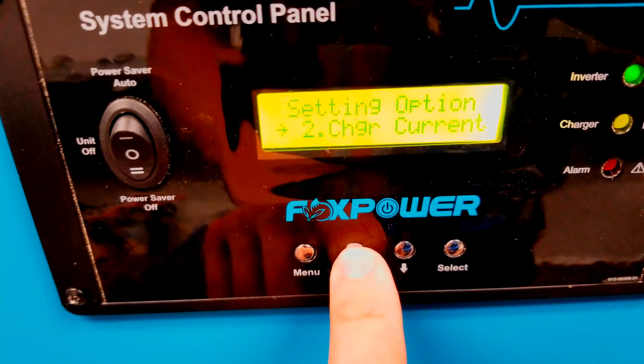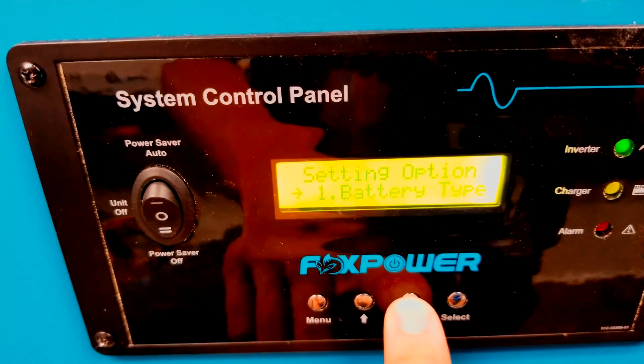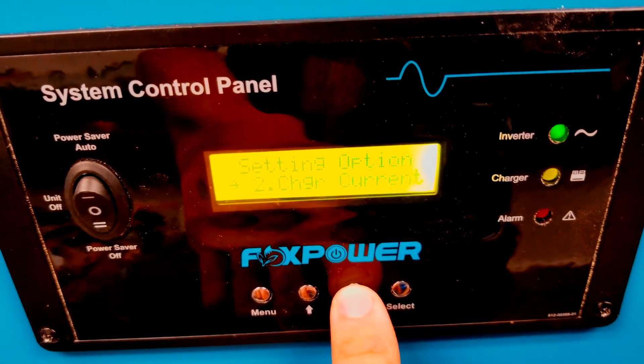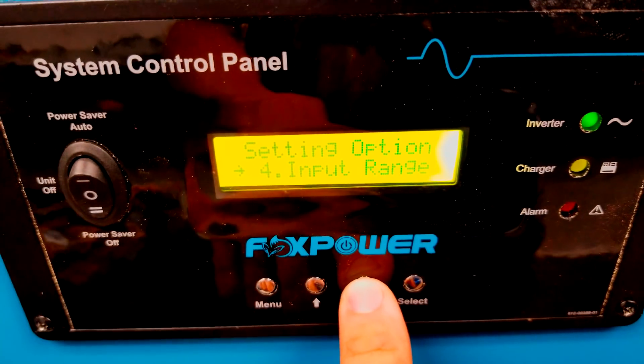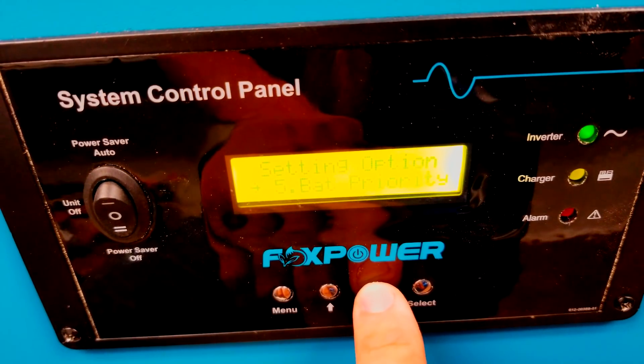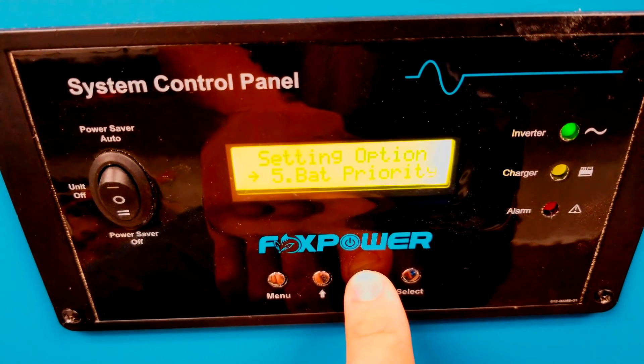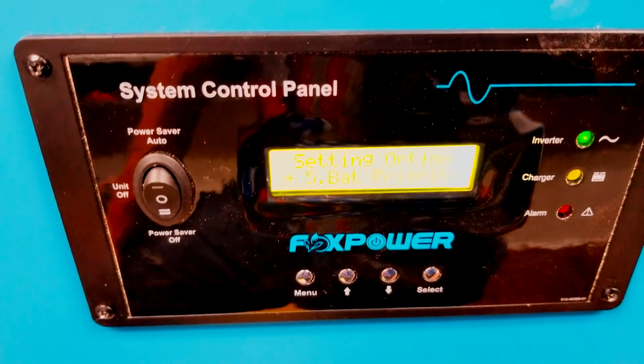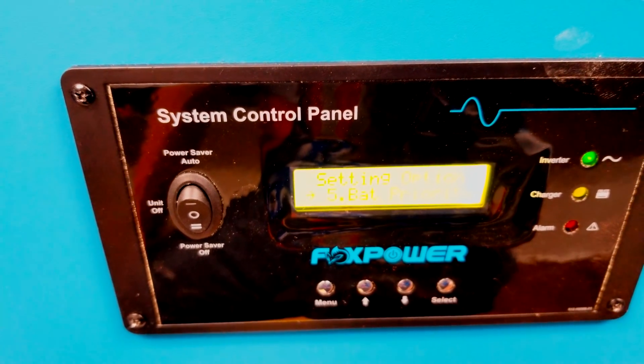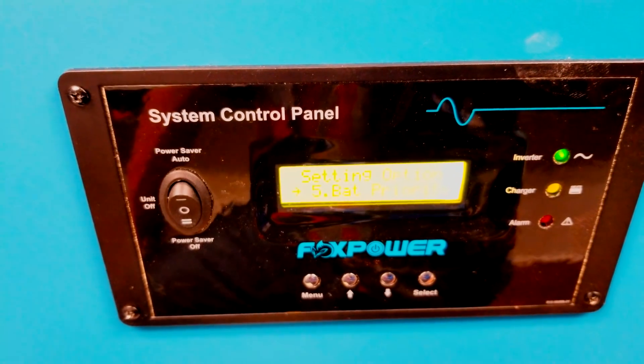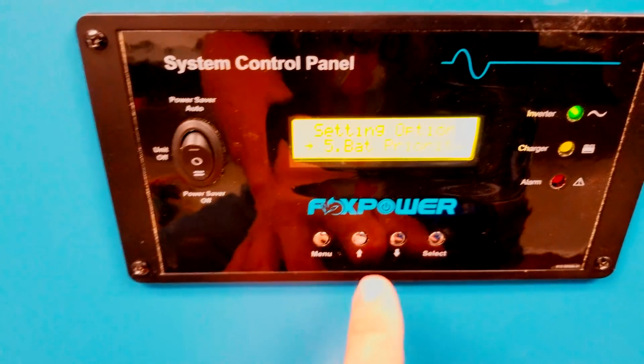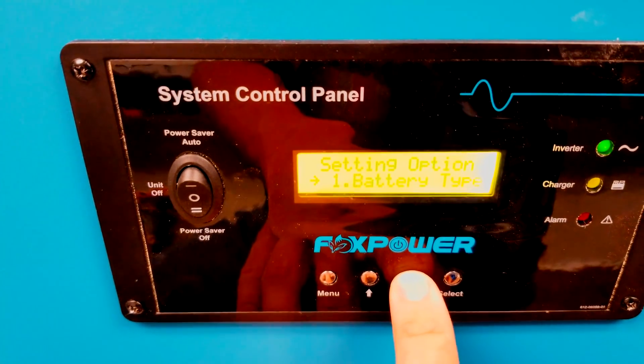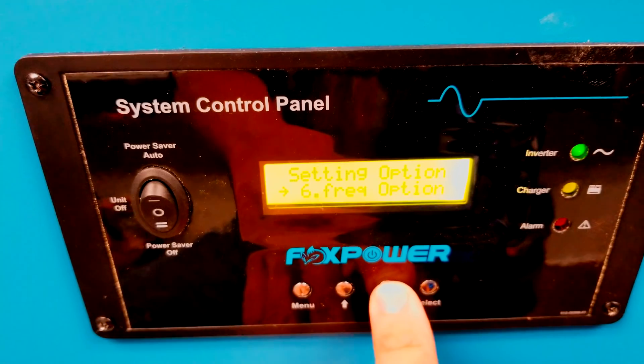And we have multiple different options. We can set our battery type, so in other words our charge voltages, our charger current, the low battery cutout, the input range—so what voltage it'll accept from the generator—and battery priority, which means if you want it to always be using the batteries, like if you're using this kind of like a UPS, or whether you're using it for solar or off-grid, that would be what you'd set that for. And also frequency options, so 50 or 60 hertz this unit will do.